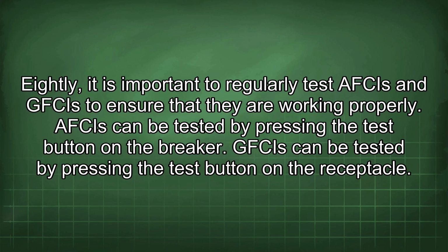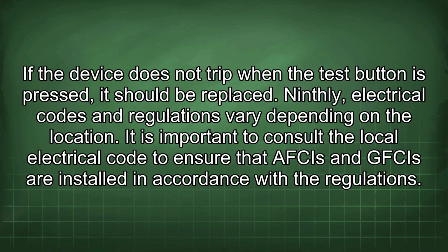AFCIs can be tested by pressing the test button on the breaker. GFCIs can be tested by pressing the test button on the receptacle. If the device does not trip when the test button is pressed, it should be replaced.